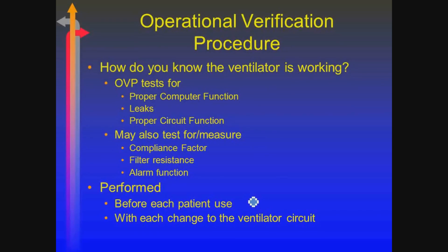What it looks for is it looks to make sure the machine, because again, this is a piece of silicon, right? Want to make sure that it's functioning. Last thing you want to have is a ventilator that malfunctions. So is the computer working? It detects for leaks in the circuitry, so if there's something where some connection isn't tight, it'll tell you that.